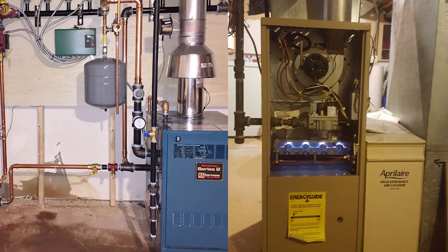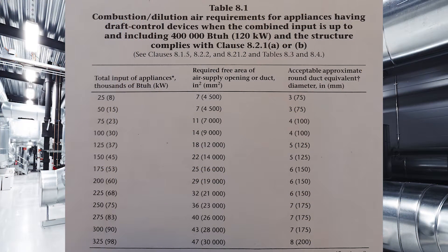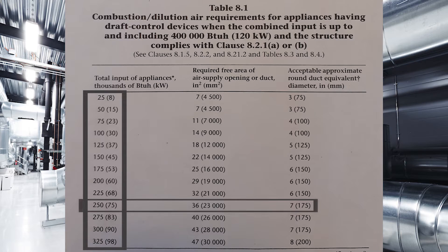My example will be a 250,000 BTU drafthood equipped boiler and a 100,000 BTU fan-assisted furnace together. We begin at table 8-1 with drafthood equipped appliances only. The total on that is 250,000 BTUs, so we go down to 250 on the left-hand column, come across to the right, and we need a 7-inch round air supply. We'll jot that down to reference later.